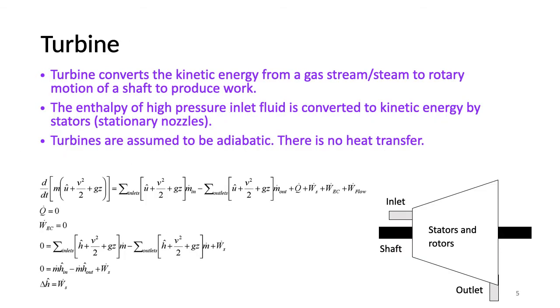Turbines. Turbine is an equipment that converts the kinetic energy from a gas stream or steam flow into rotary motion of a shaft to produce work. The enthalpy of high pressure inlet fluid is converted to kinetic energy by stators. Stators are placed inside the turbine and are stationary. They are a type of nozzles that increase the kinetic energy of the incoming fluid stream. The high velocity gas stream then drives the rotor.